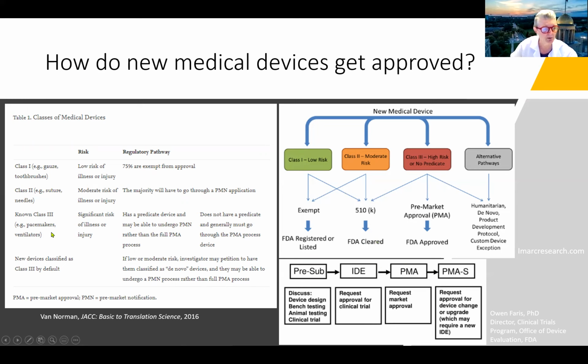Now, there's class 3, which is where a lot of things in EP fall into, which is significant risk of illness or injury. And that would be things like pacemakers or new ablation catheters. Now, if there is a predicate device that's already been approved, and again, it's very, very similar, for instance, you just have a pacemaker that has a new battery with extended longevity, and otherwise the pacemaker is really identical to a previously approved one, then even if it's in class 3, you can move over to this pre-market notification 510K and then go ahead and start marketing that.